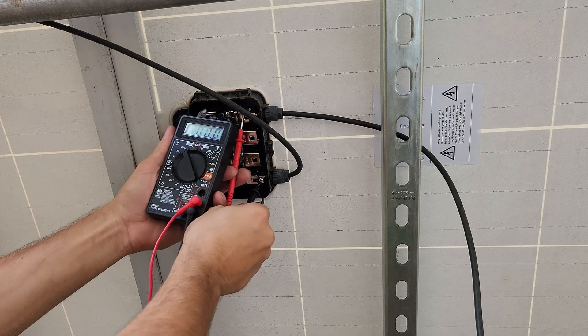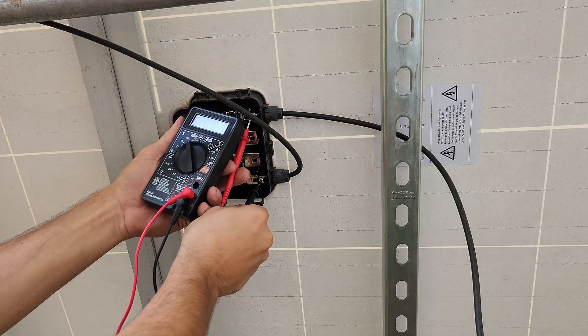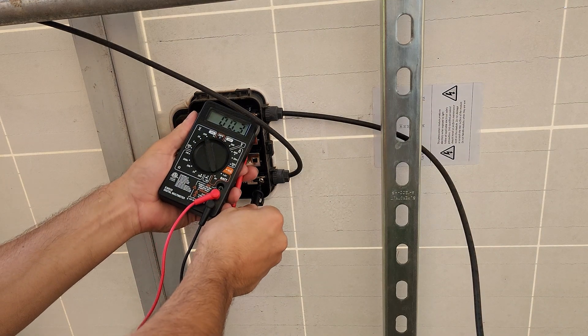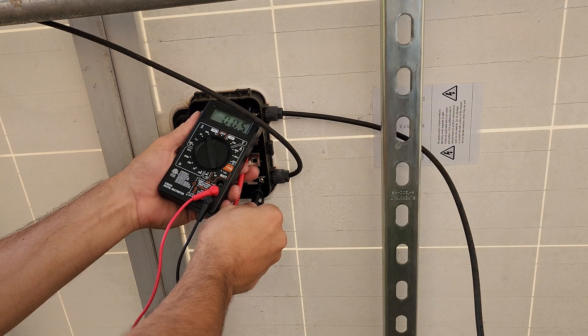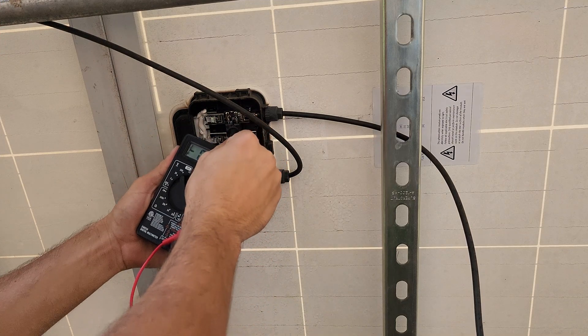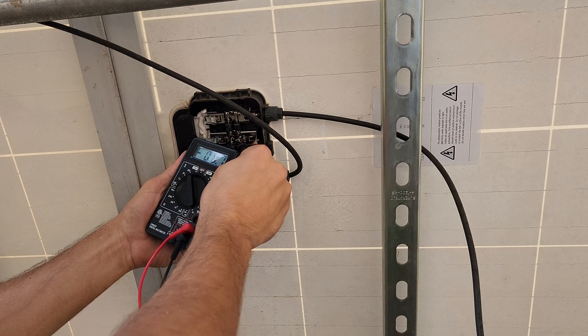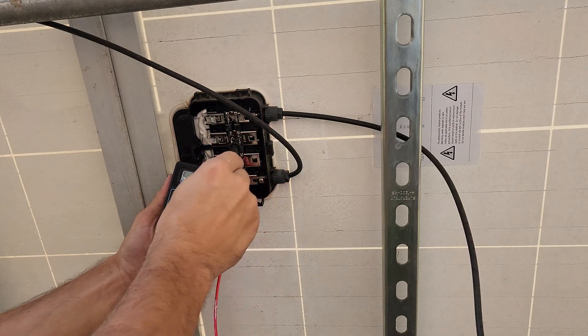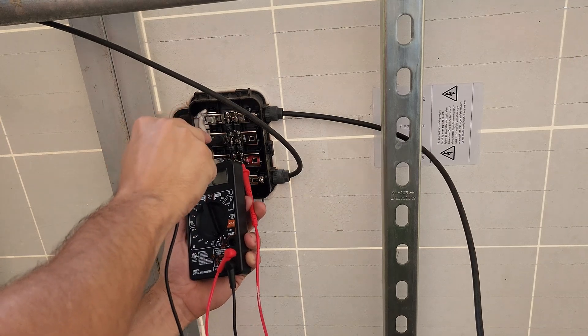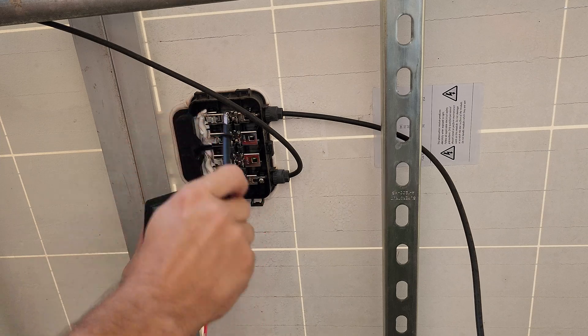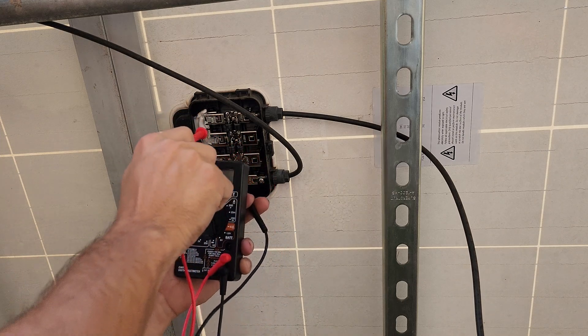As we can see, despite my terrible camera angle, we have zero volts coming through the terminals on the panel. We should be seeing somewhere around 40 volts, so zero is definitely bad. We can swap over to the diode testing function and see that the diodes are allowing power to go through the diode on both sides. I believe this means that it failed open - not 100% sure on the terminology there, I just know how to replace it.